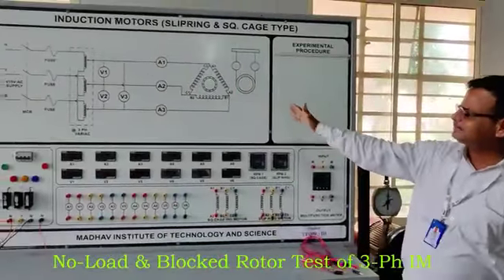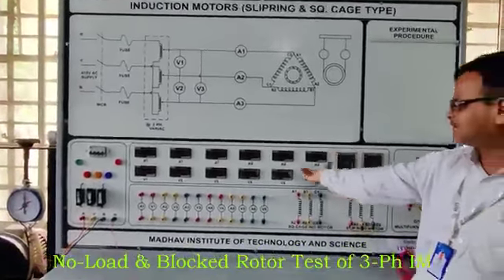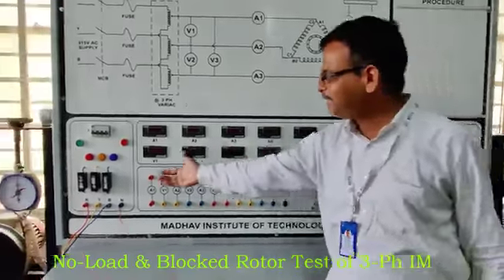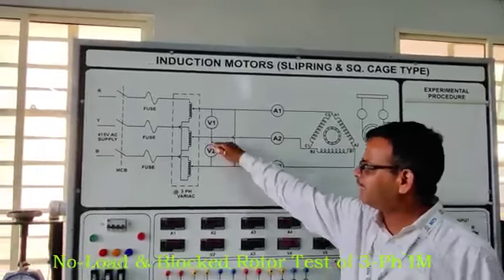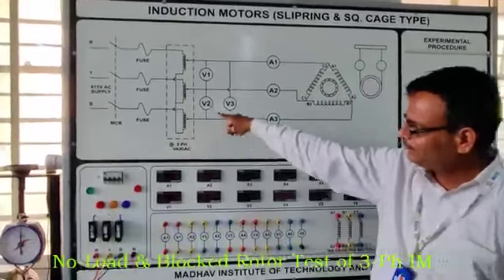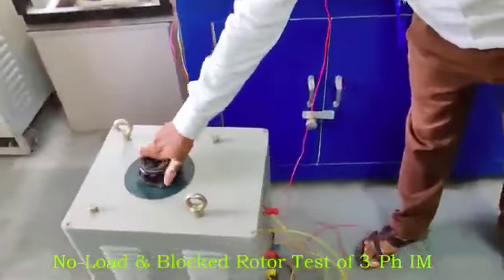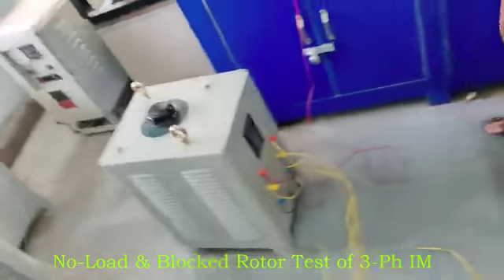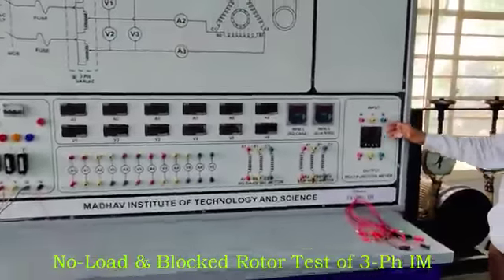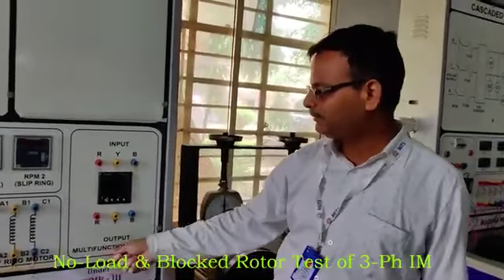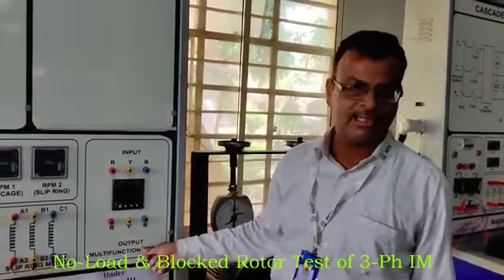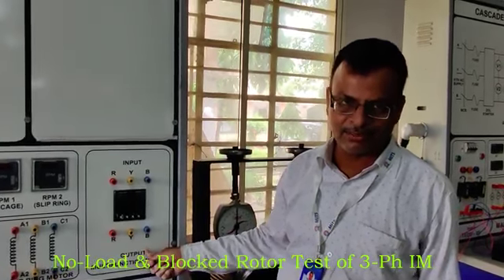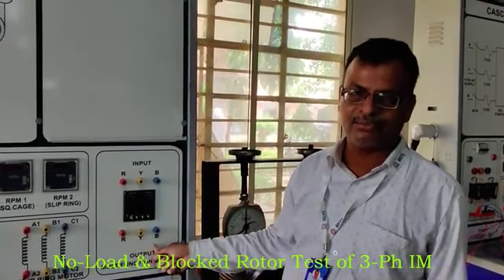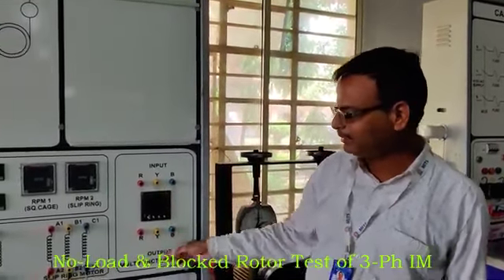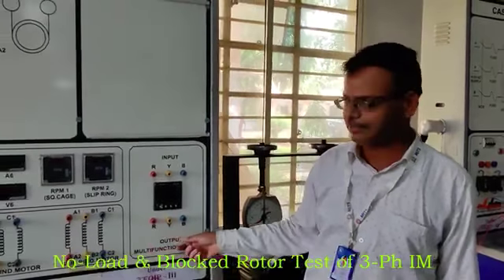So this is the panel. In this panel, the different ranges of ammeters and voltmeters are given here. An MCB switch is given here, and a circuit diagram is given here. This circuit diagram has the symbol for the 3-phase variac. This is the autotransformer or 3-phase variac, and this is the multifunction meter. It is called multifunction because you can measure all the electrical quantities like current, voltage, power factor, power, reactive power, frequency, line-to-line voltage, everything with the help of this multifunction meter. That's why it is called multifunction.